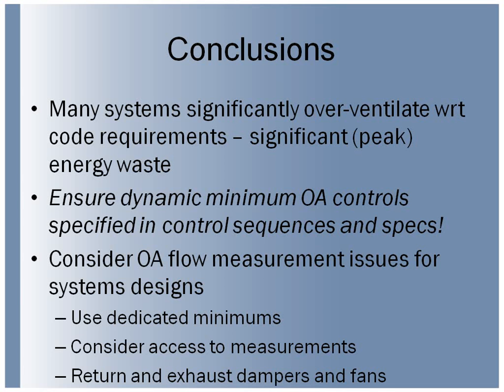So some of the conclusions here, we noticed obviously that many systems significantly overventilate, especially during peak flows, peak times. And the takeaway from that, from my perspective, and being in the commissioning business, we see a lot of these sequences. We need to make sure that the spec for sequence of operation that includes dynamic minimum ventilation control is included in all of our projects. And it's kind of implicit in Title 24 for California, but not necessarily explicit.